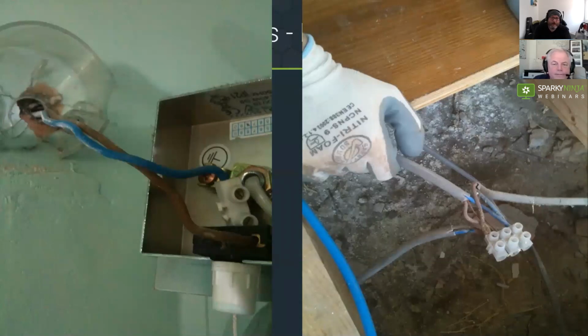What about the one on the right here? Cable underneath - this is a connection under the floor, so it's not accessible, it's a void space. So are we going to give that a C2 or a C3? What is the potential danger here? For me personally, I'd C2 it, and the reasons are those terminals are screw type terminals - they can become loose. As the circuit comes under use, the cables heat up, expand and contract, heat up, expand and contract.